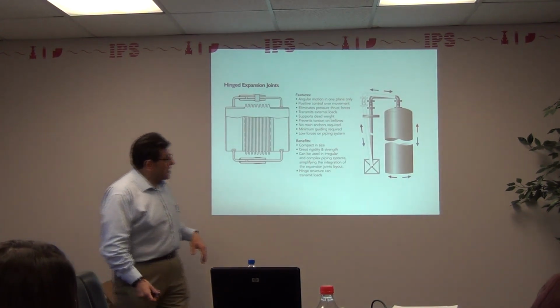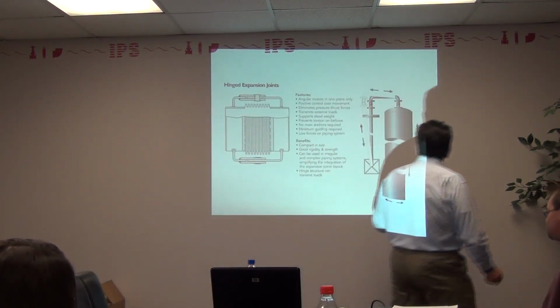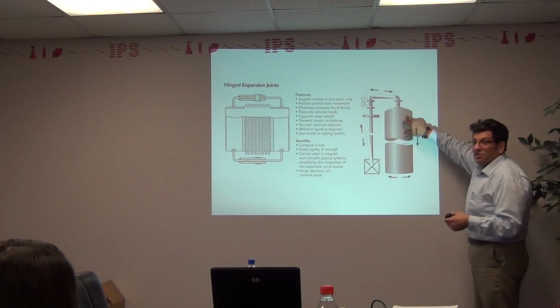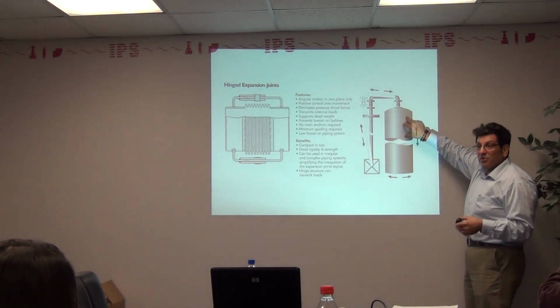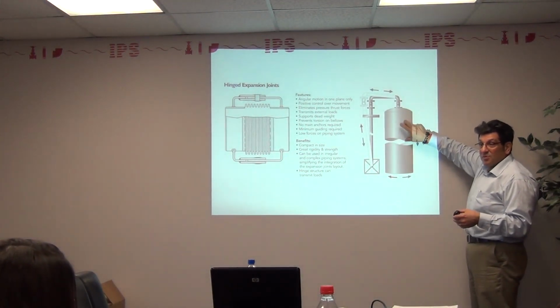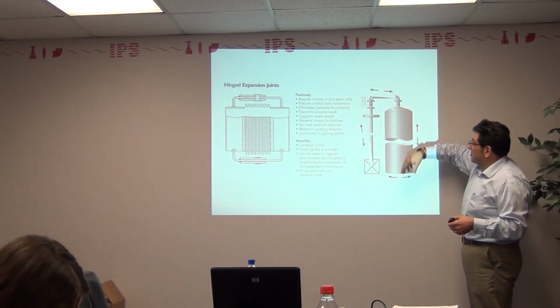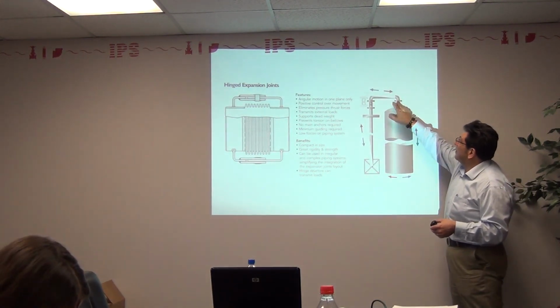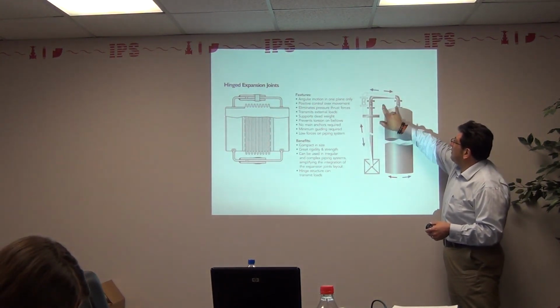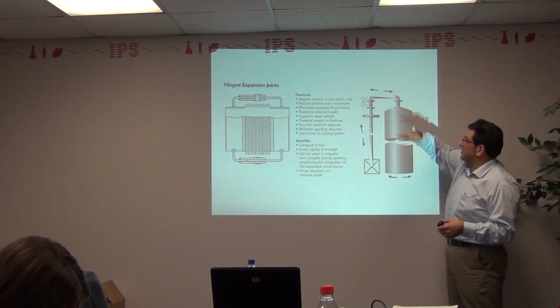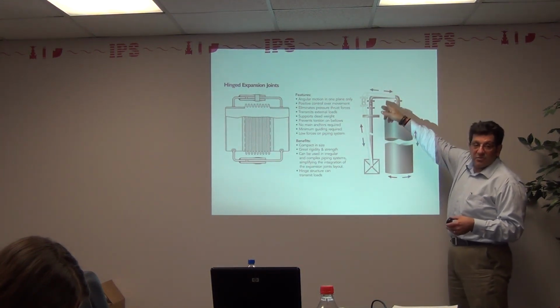So you look at a load cell or a tank, something like that. The tank itself is going to grow - it's a steel tank, it's going to expand and contract, and it's going to actually turn. Same for the piping. So here we're going to handle that motion independent of each other. We use a couple of hinged expansion joints, because that's what that pipe's going to do.